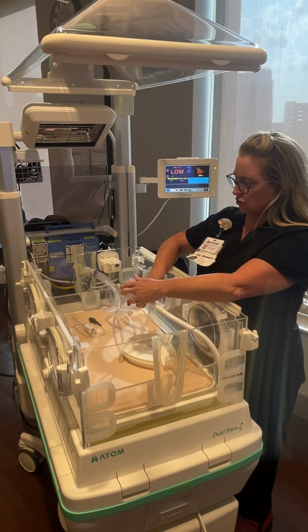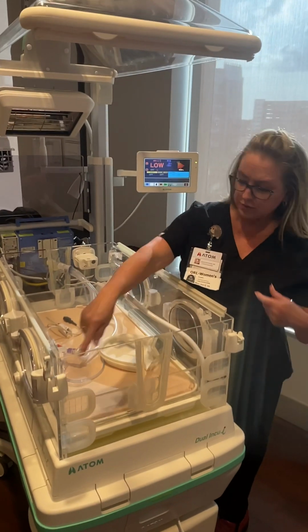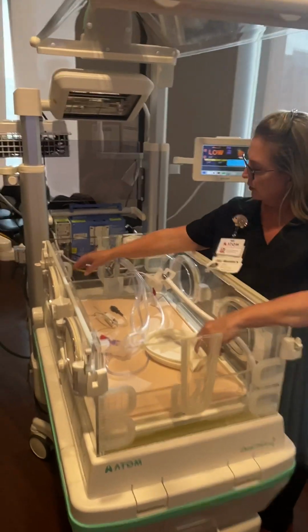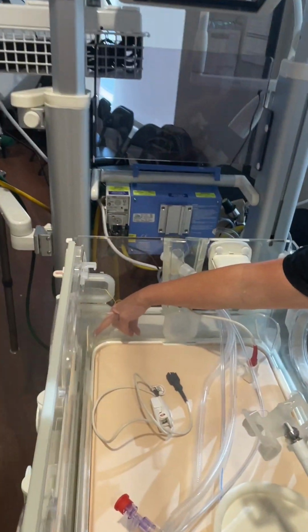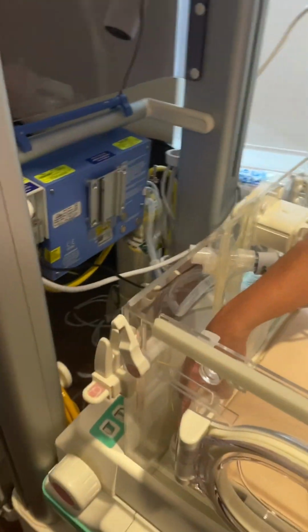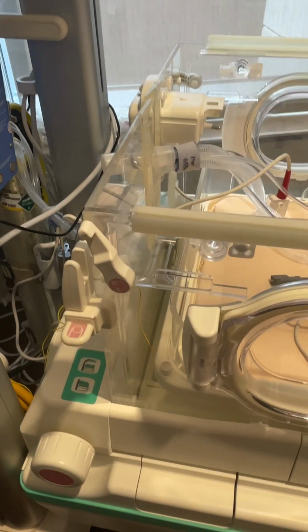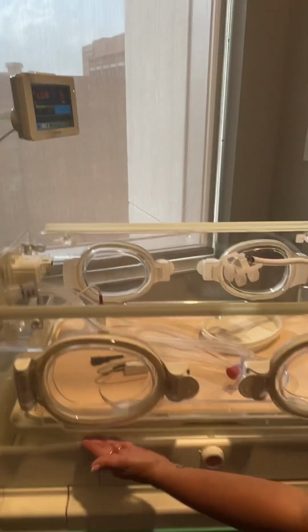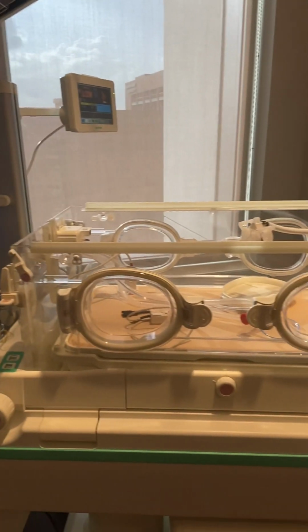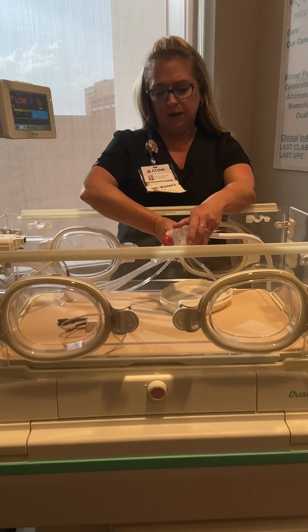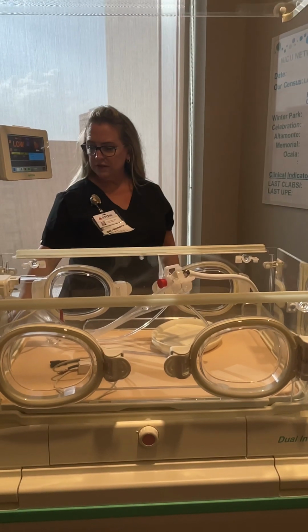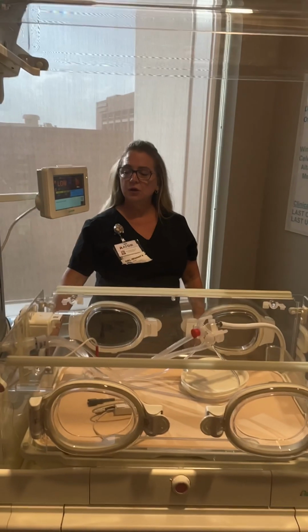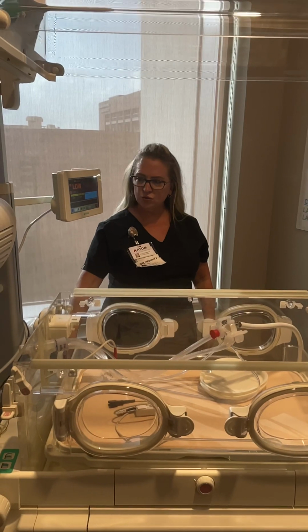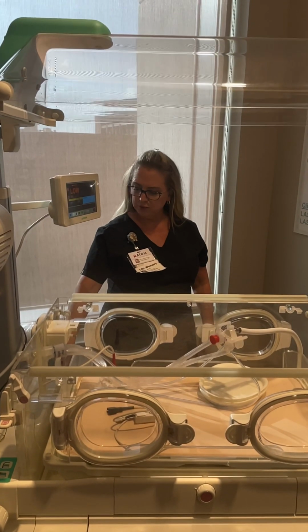And it screws in from the bottom, and you can just move it to any of the little side ports. Right here is a bubble level for your mattress surface level. It's a target level, but I always look at the sight lines here to see if it's completely perpendicular. That's how I like to do it, so I can adjust my level here to make sure it's flat. And now we'll have the descent here. Press and hold, and it will again transform back into the warmer mode, or the incubator mode.